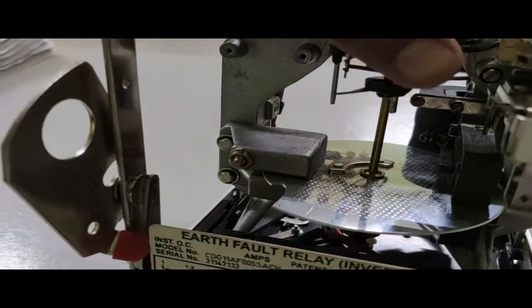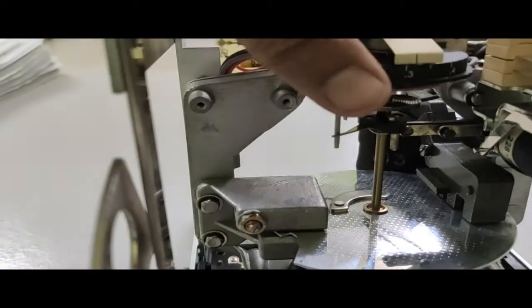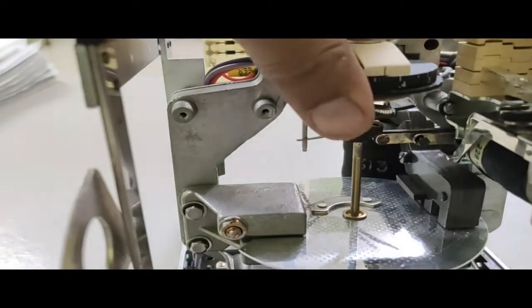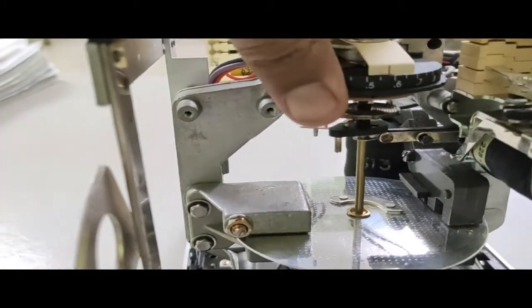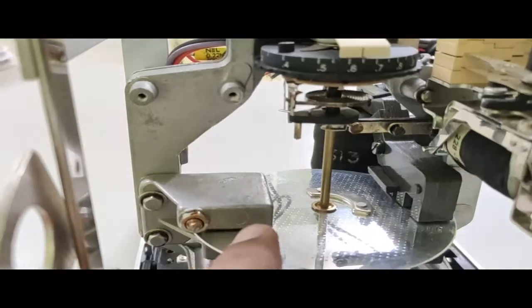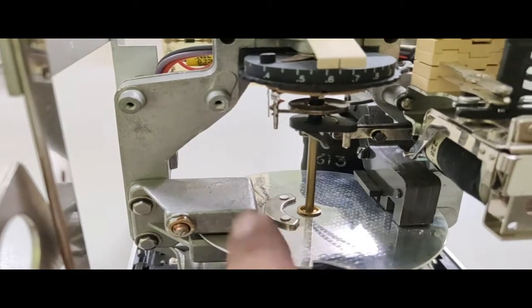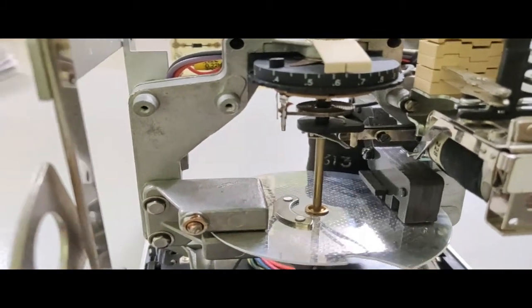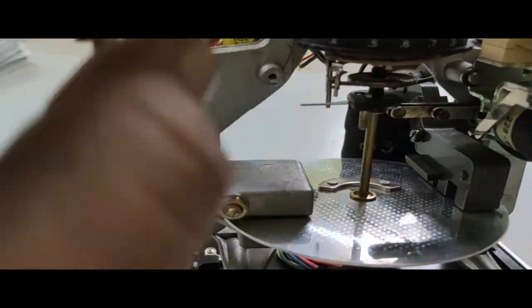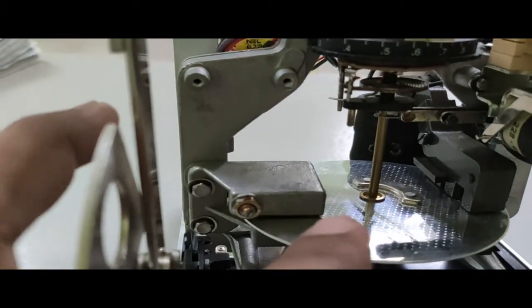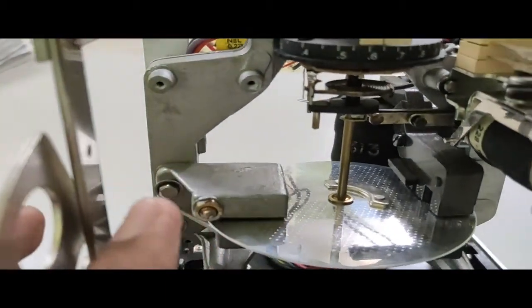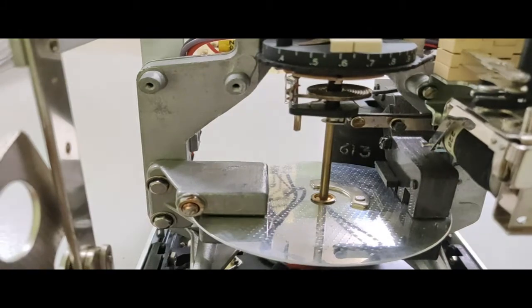But if I move the time setting multiplier in the clockwise direction, then you see that part goes beyond, and here the disc needs to travel a lot to generate the trip signal. So just by adjusting the backstop, that is, setting the initial position of the disc, we can adjust the time of operation of the relay.